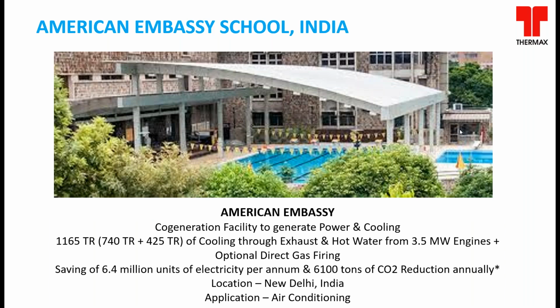Similar to the American Embassy, there is an American Embassy school in New Delhi, where air conditioning is done by heat recovery from engine exhaust gas and jacket water. We have 2 chillers, 740 TR and 425 TR, working on heat recovery from 3.5 megawatt gas engines, with backup firing capability for engine-off conditions.